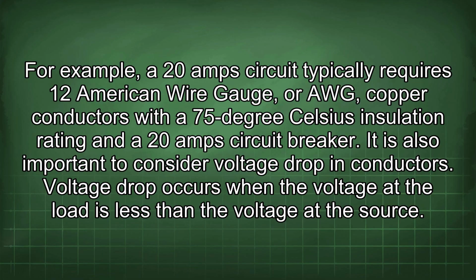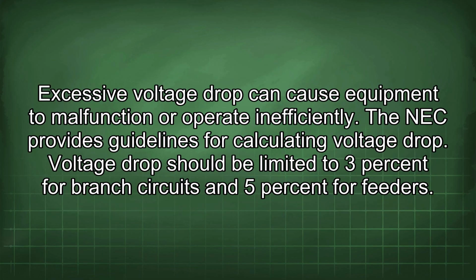It is also important to consider voltage drop in conductors. Voltage drop occurs when the voltage at the load is less than the voltage at the source. Excessive voltage drop can cause equipment to malfunction or operate inefficiently. The NEC provides guidelines for calculating voltage drop. Voltage drop should be limited to 3% for branch circuits and 5% for feeders.